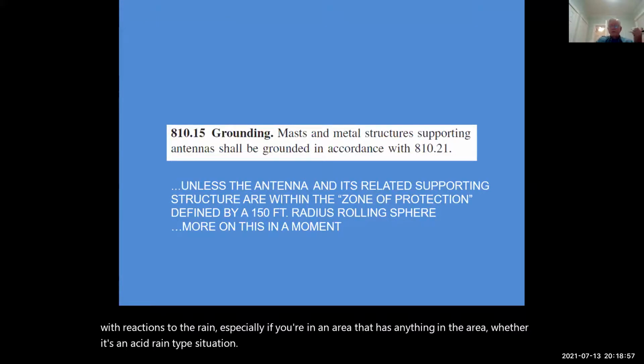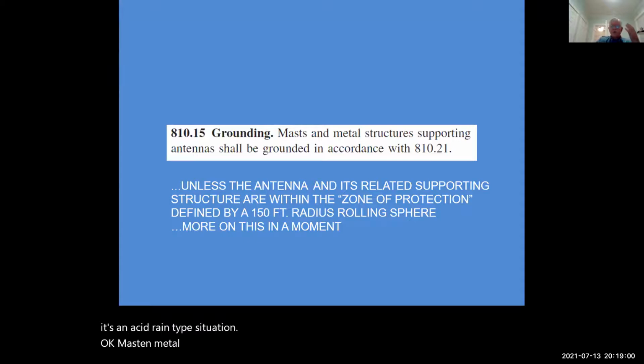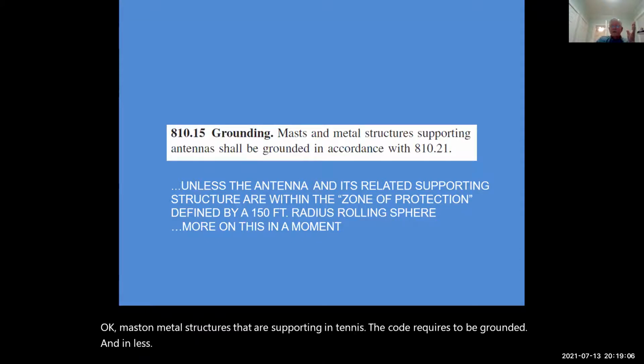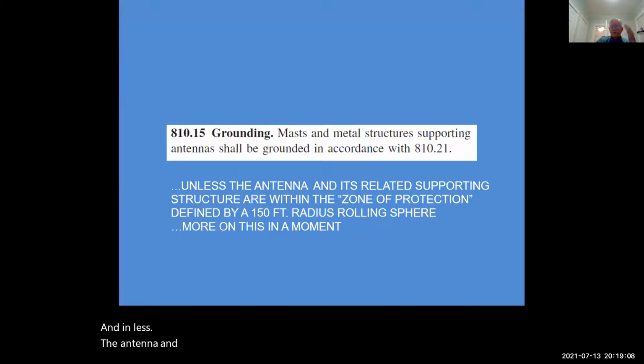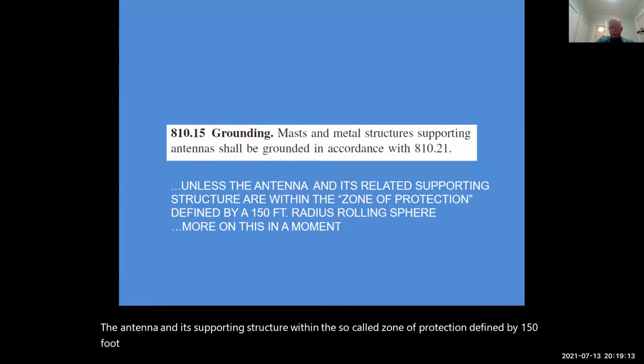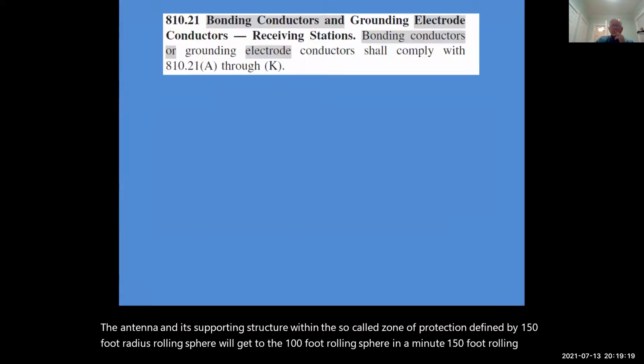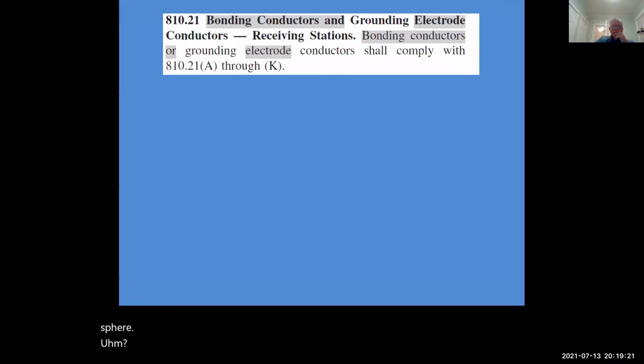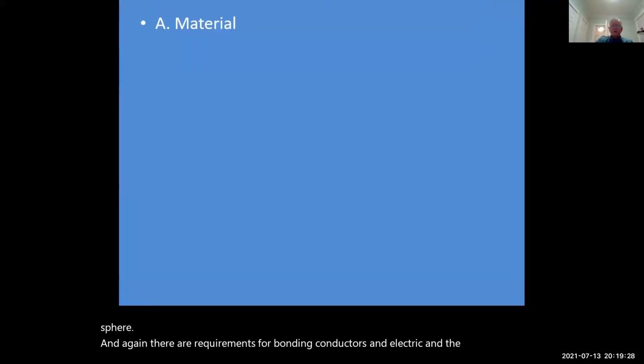Masts and metal structures that are supporting antennas, the code requires them to be grounded, unless the antenna and its supporting structure are within the so-called zone of protection defined by a 150-foot radius rolling sphere. And we'll get to the 100-foot rolling sphere in a minute, 150-foot rolling sphere. Again, there are requirements for bonding conductors and the ground electrode conductors.